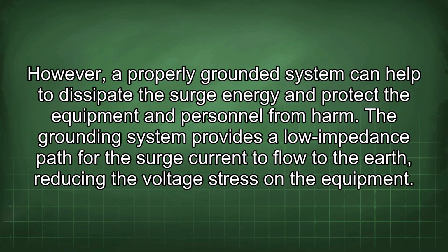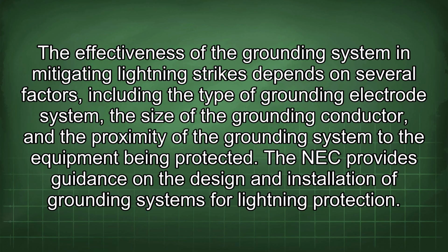However, a properly grounded system can help to dissipate the surge energy and protect the equipment and personnel from harm. The grounding system provides a low impedance path for the surge current to flow to the earth, reducing the voltage stress on the equipment. The effectiveness of the grounding system in mitigating lightning strikes depends on several factors, including the type of grounding electrode system, the size of the grounding conductor, and the proximity of the grounding system to the equipment being protected. The NEC provides guidance on the design and installation of grounding systems for lightning protection.